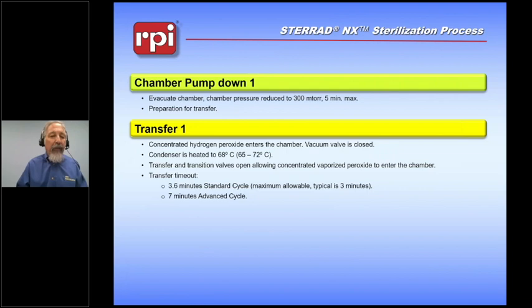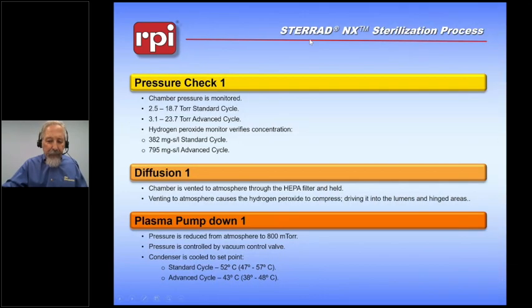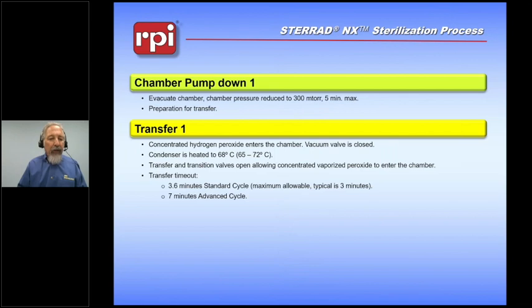Chamber pressure. We need to look at the chamber to make sure that when we transfer the condensed hydrogen peroxide, the pressure in the chamber is lower than the pressure in the vaporizer condenser assembly, and that allows the peroxide to move from the higher pressure to the lower pressure, thus filling the space within the chamber and spreading out throughout all the various spots we're trying to reach. The transfer time, we keep the valves open for a specific period of time, and we keep the condenser heated to a correct temperature so that none of the peroxide condenses within the transfer system.